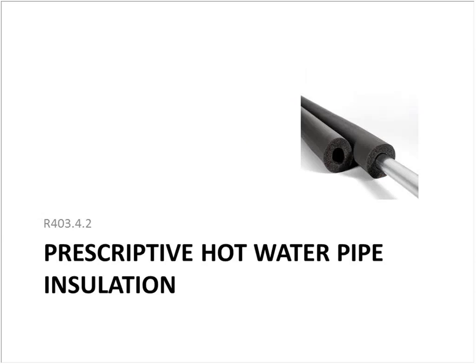Insulation for hot water pipe with a minimum thermal resistance shall be applied to the following. This is an R3 piping, or R3 insulation, should be applied to the following. Piping larger than 3/4 of an inch nominal diameter. Piping serving more than one dwelling unit. Piping located outside the conditioned space. Piping from the water heater to the distribution manifold. Piping located under a floor slab or buried piping, and supply and return in recirculating systems other than demand recirculating systems.